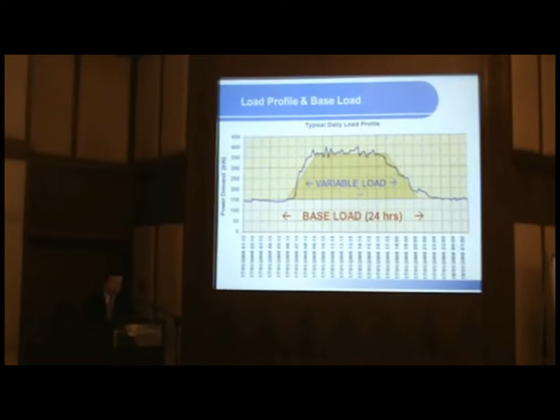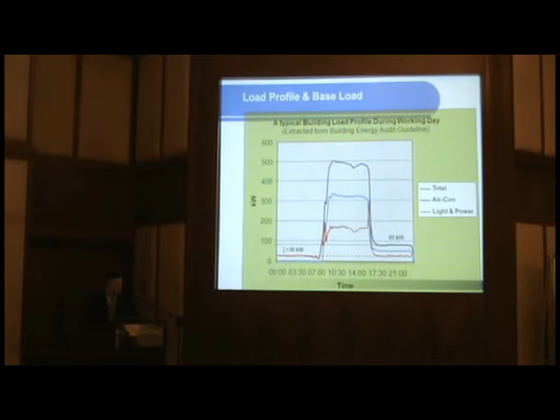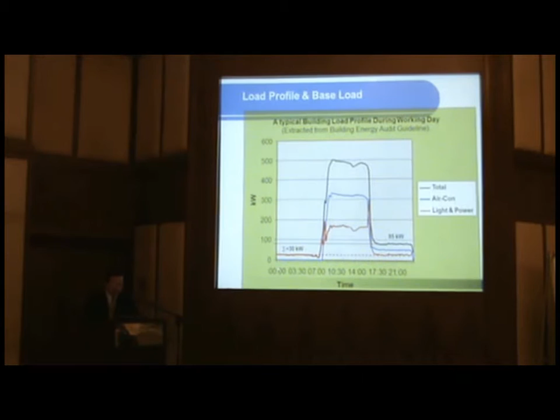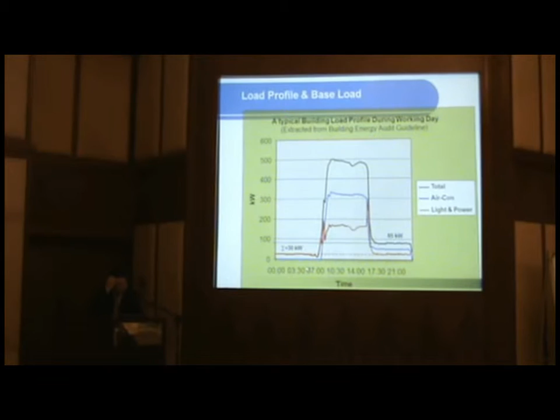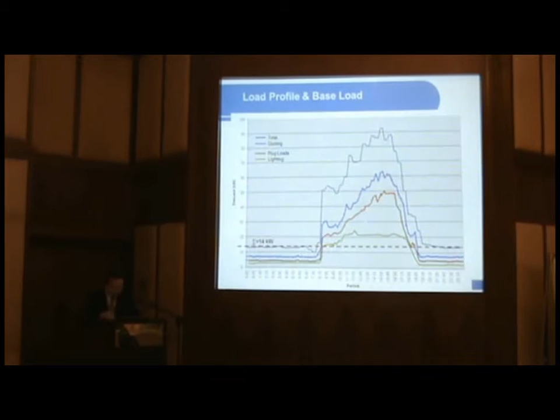This is a library. Night time, the black color is the total load. After 5 o'clock the library closes, but some load still runs. After 12 it reduces and we maintain about 30 kilowatts. When we did the energy audit, we found that part of the 30 kilowatts is the water pump running.